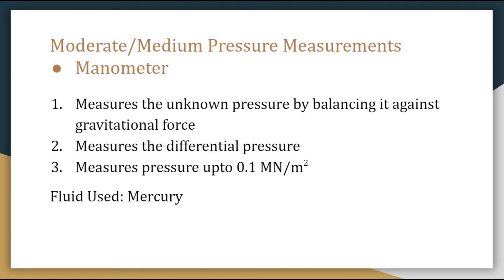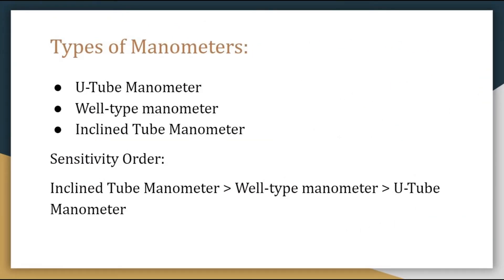The fluid kept inside a manometer needs to have low viscosity, low thermal coefficient of expansion, it should be non-corrosive and non-sticky, it should have low surface tension and low vapor pressure as well. An example of such a fluid is mercury. Mercury is widely used as a manometric fluid because of its wide temperature operating range from minus 20 degrees C to 350 degrees C, and it meets all the criteria for being a manometric fluid.